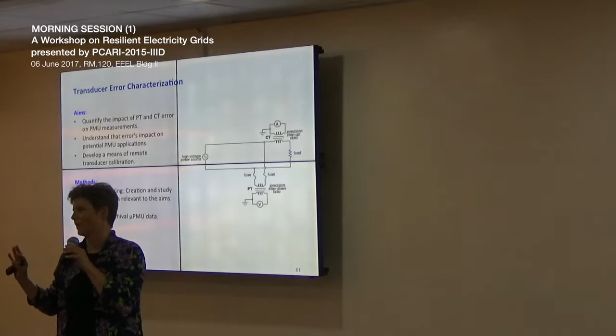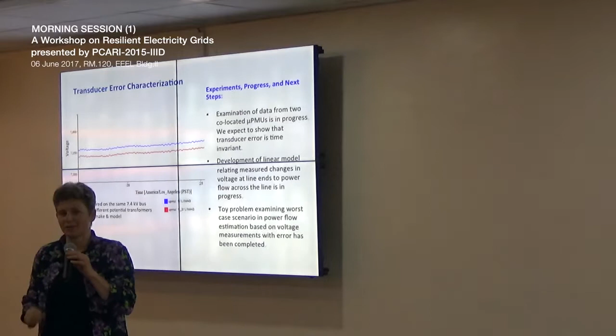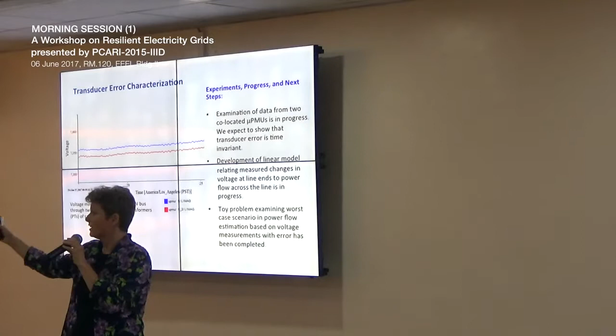This is an example of the voltage measured at the same bus through different potential transformers, same make and model, showing two different numbers. They track each other nicely, but it's as if one has a different ratio than the other. The difference isn't huge — a few tens of volts on a 7.4 kV base — but if what you're looking for is a difference in voltage between two nearby points, then it matters.